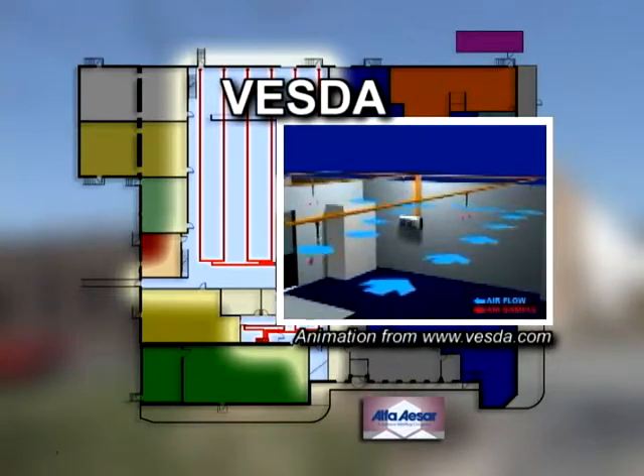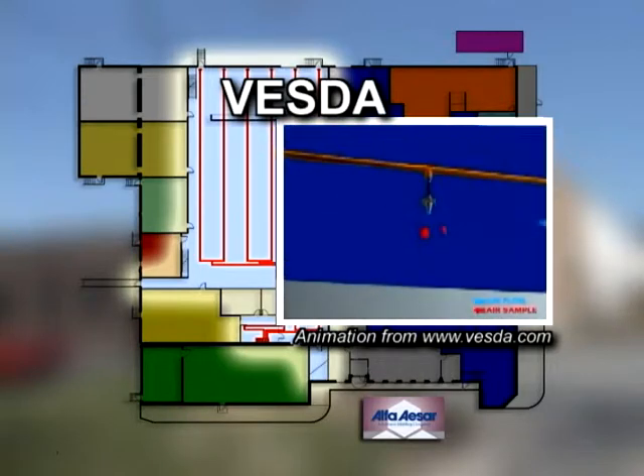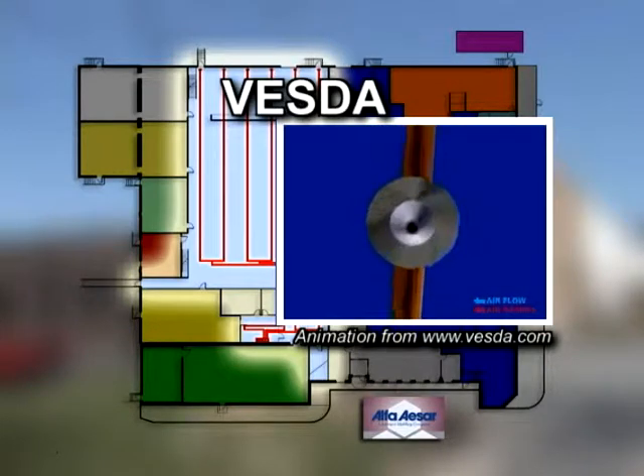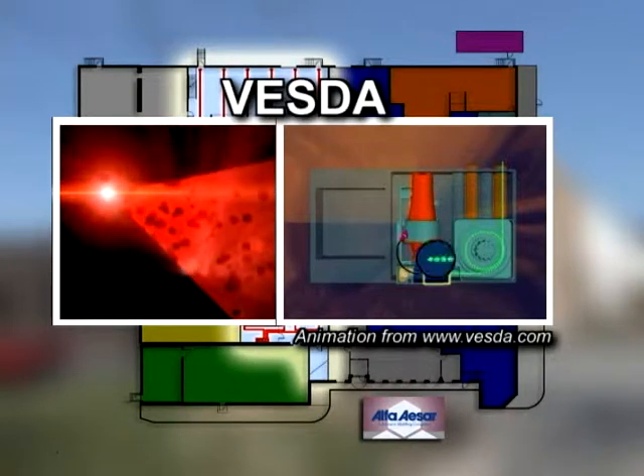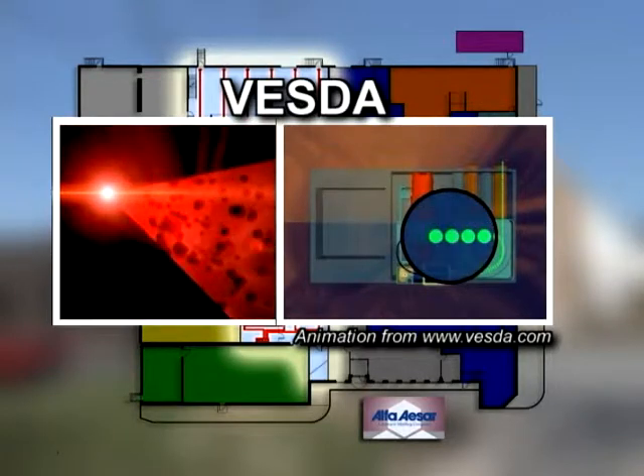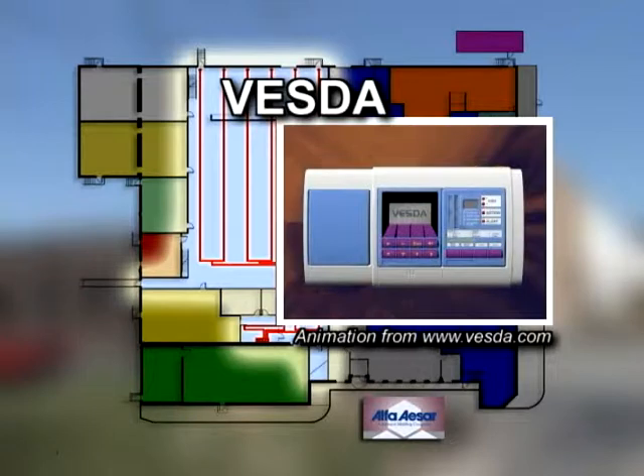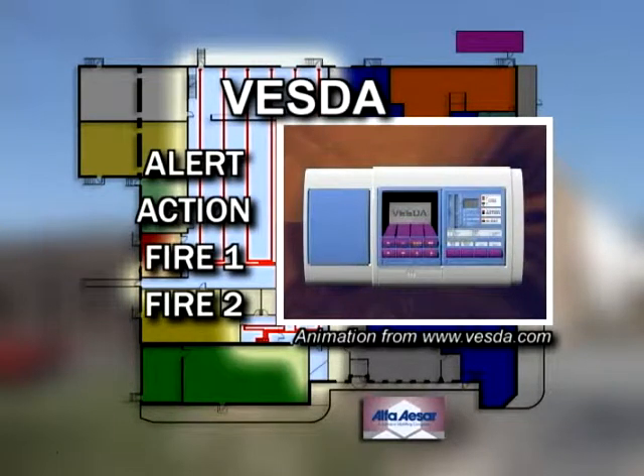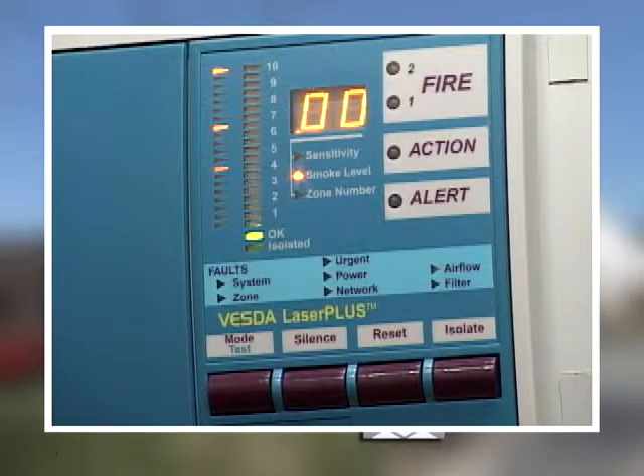The particular product that is used in Zone 7 is the VESDA Laser Plus series detector. This unit operates by continually drawing air from the protected environment through a high-efficiency aspirator and a 4-pipe sampling network. The air sample is then exposed to a laser beam within the detector's sample chamber. The presence of smoke particulate causes light scattering within the unit's sample chamber and, in turn, is detected by a receiver circuit. The signal is processed and sent to the unit's display that will indicate the level of smoke particulate in the sample. When the unit detects even minute-sized smoke particulate, the level will indicate on the active smoke level display and will activate predetermined Alert, Action, Fire 1, and Fire 2 relay contacts. The VESDA Laser Plus is also equipped with multiple supervision relay options, including system fault, power loss, and relay disable.